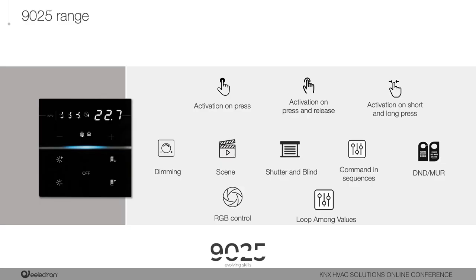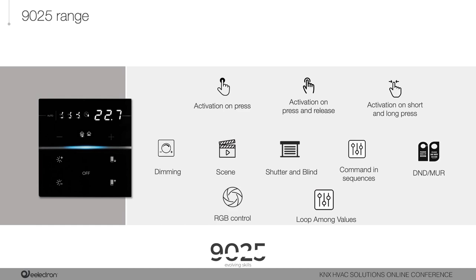The button functions available for the 9025 range include common ones such as activation on press, activation on press and release, activation on short and long press, dimming, scene management, and shutter and blind control. Advanced functions include DND and make-up room, command in sequences, loop among values — which allows sending different values over a one-byte telegram — and RGB control, enabling direct control of an RGB driver using only one button.